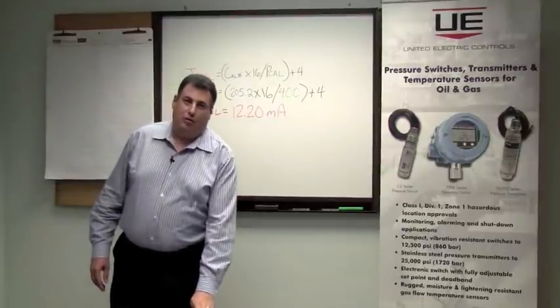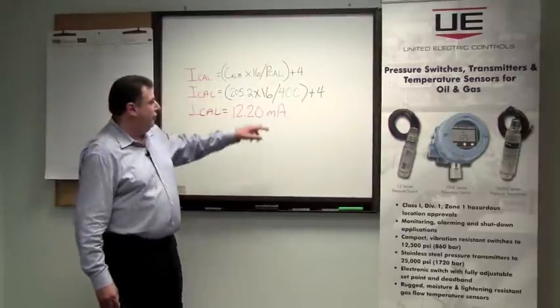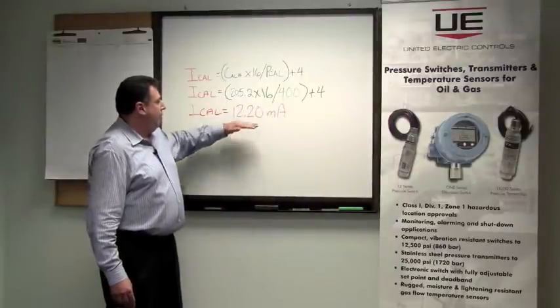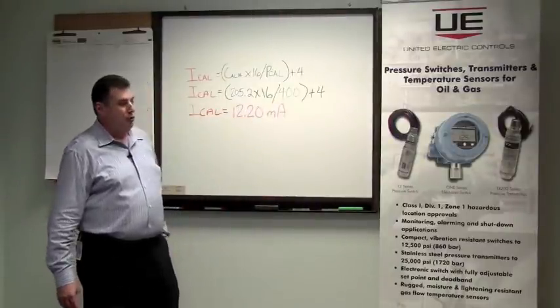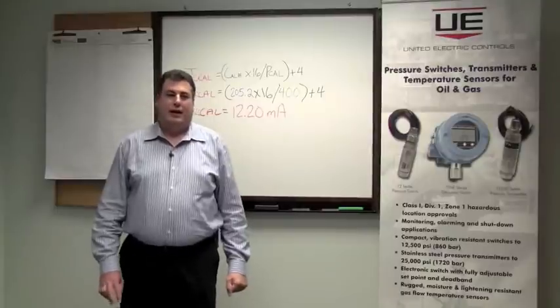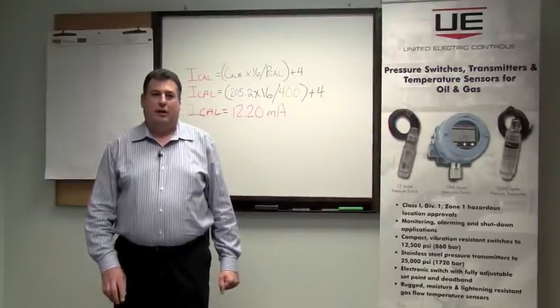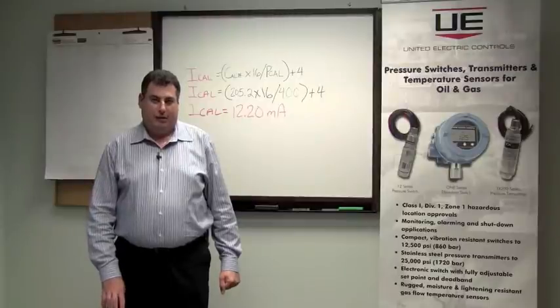So each TX200 has a 5 to 1 turn down. As I explained, we're turning it down to 400 psi, and the ICAL is 12.20 milliamps. The ICAL value is the milliamp current that we'll need to see when we're making our adjustments to the TX200.